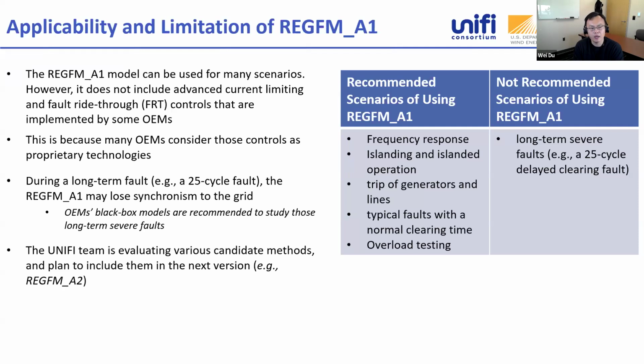But we don't recommend using this model to study long-term severe faults, like delayed clearing faults. This is because this model is a generic model. It does not include all the details from manufacturers. We appreciate the information manufacturers provided to develop these models, but there are some proprietary technologies that are not reflected in this model.